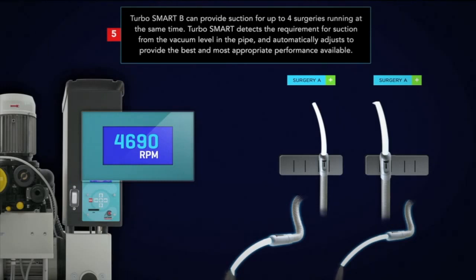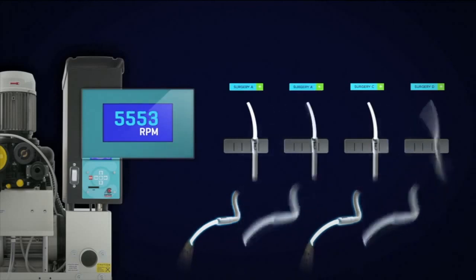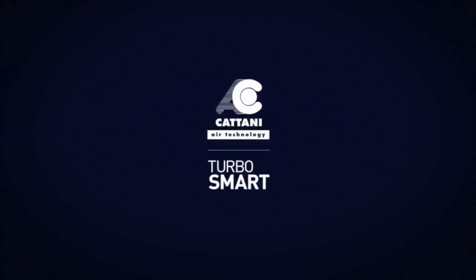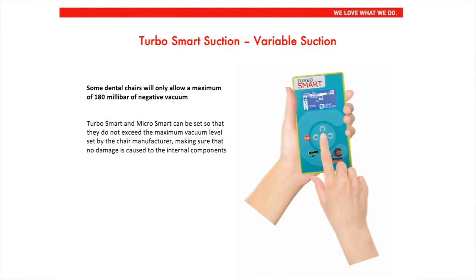TurboSmart detects the requirements from the surgeries from the vacuum level in the pipework and automatically adjusts to provide the best and most appropriate performance available. This is why it's very important to have the correct pipework layout in your practice. Most of the problems we hear about from customers are generally down to incorrect pipework runs and sizes. Some dental chairs will only allow a maximum of 180 millibar of negative vacuum. TurboSmart and Microsmart can be set so that they do not exceed the maximum vacuum level set by the chair manufacturer, making sure that no damage is caused to the internal components.